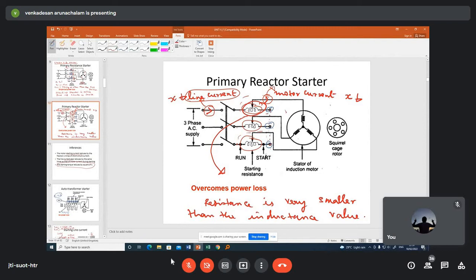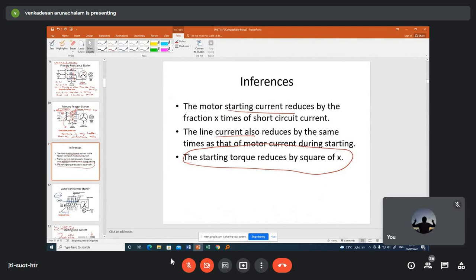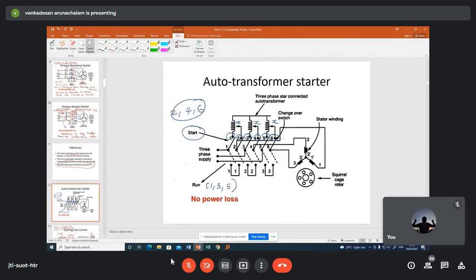So what is the advantage of the auto transformer starter? Sir, first you used the primary resistance starter, so their power loss is more. Yes, of course, because you are adding some extra resistance. So definitely it enhances the copper loss a little, which leads to a reduction in efficiency. That is very clear. Then people went for the primary reactor starter. Of course, the resistance is very small when compared to the reactance. So here the power loss is very much reduced when compared to the primary resistance starter. Next, the auto transformer starter also uses inductance only. Here also there is no power loss. Power loss is very minimal, similar to the primary reactor starter.